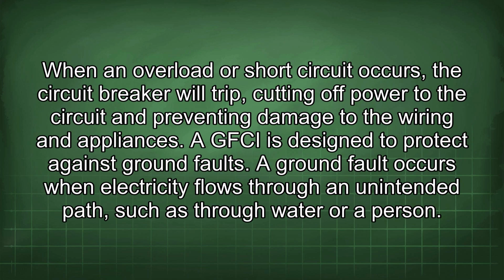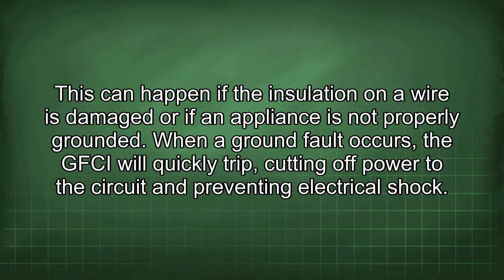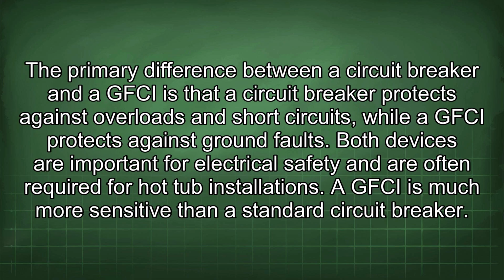When an overload or short circuit occurs, the circuit breaker will trip, cutting off power to the circuit and preventing damage to the wiring and appliances. A GFCI is designed to protect against ground faults. A ground fault occurs when electricity flows through an unintended path, such as through water or a person. This can happen if the insulation on a wire is damaged or if an appliance is not properly grounded. When a ground fault occurs, the GFCI will quickly trip, cutting off power to the circuit and preventing electrical shock. The primary difference between a circuit breaker and a GFCI is that a circuit breaker protects against overloads and short circuits, while a GFCI protects against ground faults.